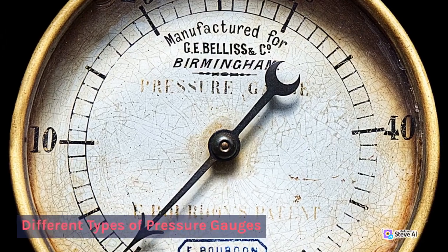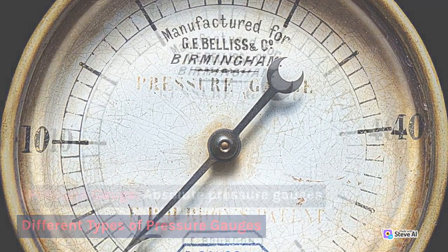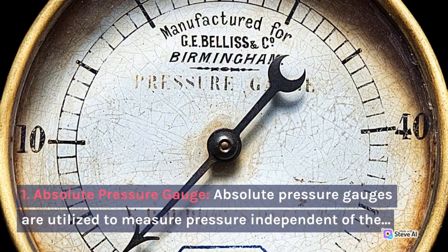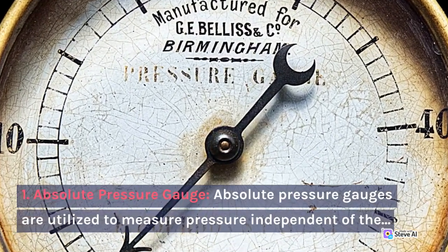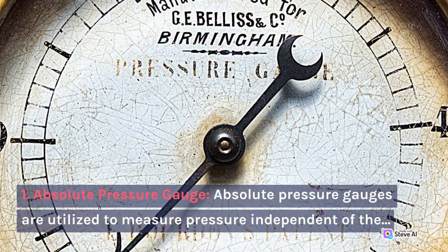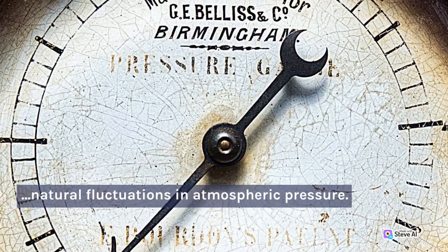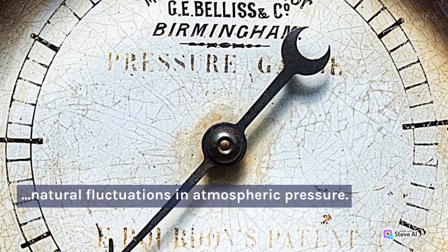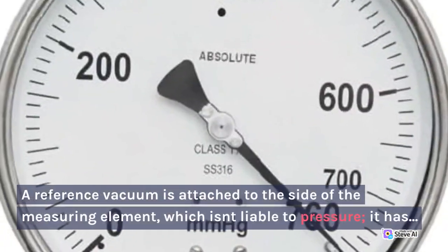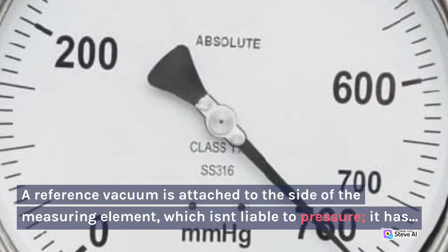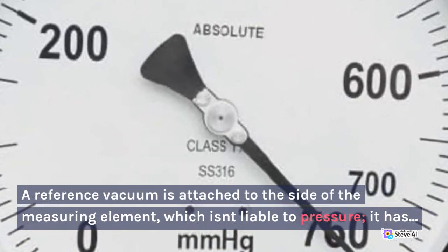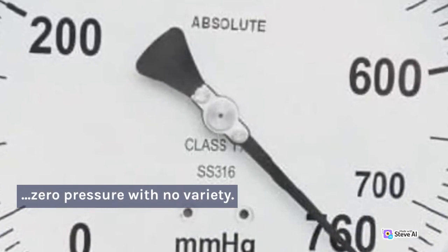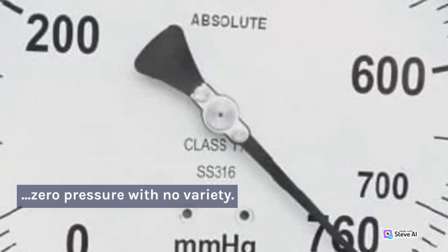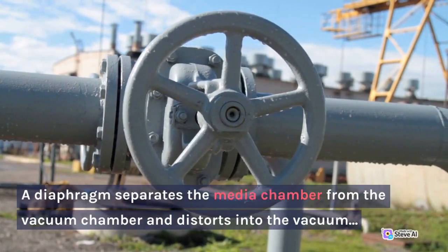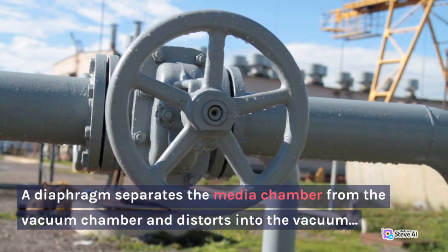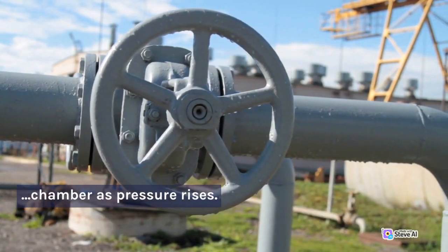Different types of pressure gauges. 1. Absolute pressure gauge. Absolute pressure gauges are utilized to measure pressure independent of the natural fluctuations in atmospheric pressure. A reference vacuum is attached to the side of the measuring element, which isn't liable to pressure. It has zero pressure with no variety. A diaphragm separates the media chamber from the vacuum chamber and distorts into the vacuum chamber as pressure rises.